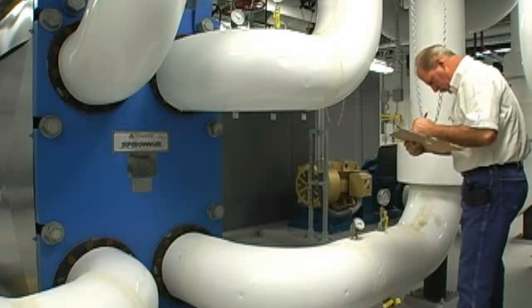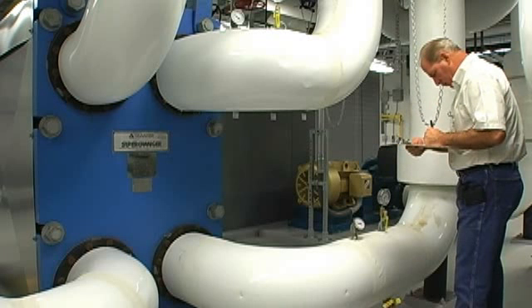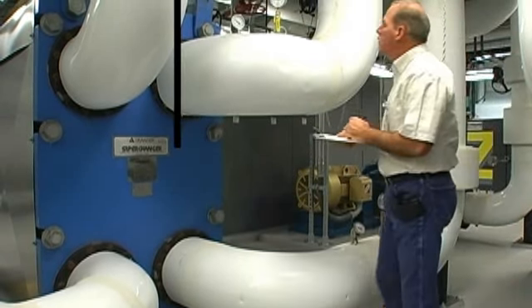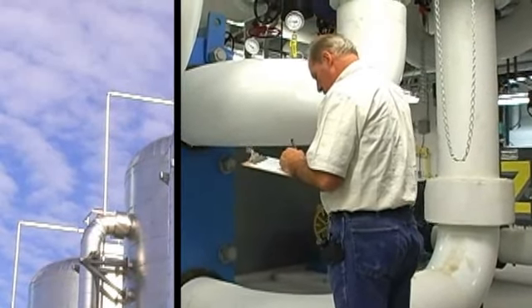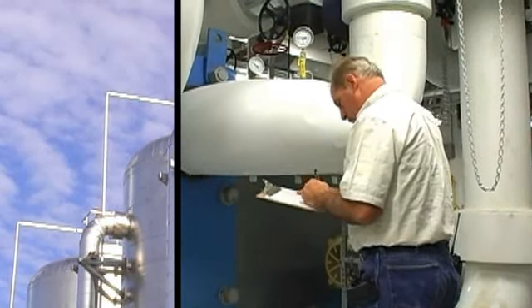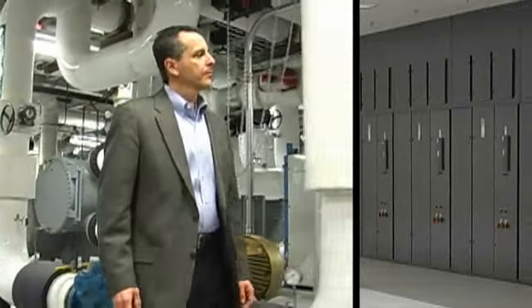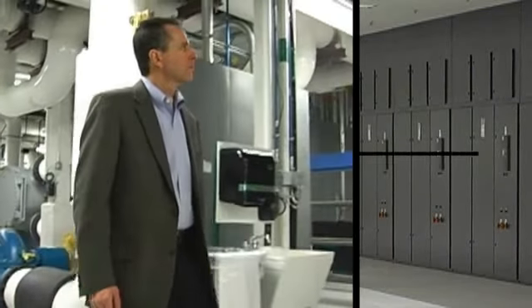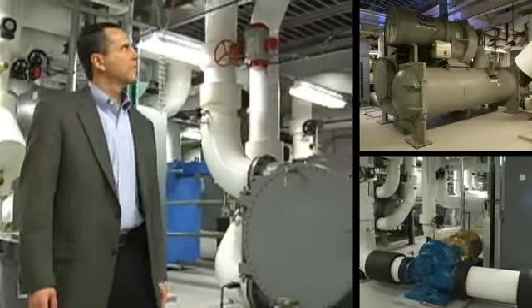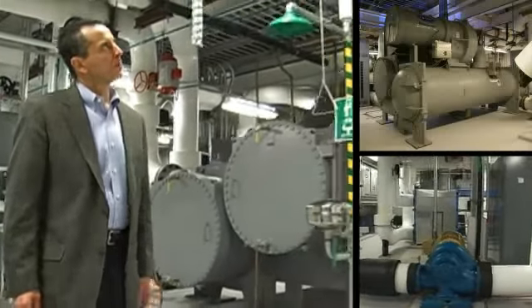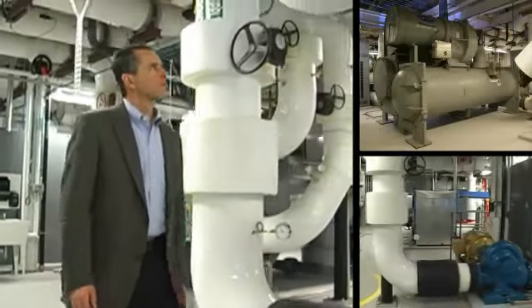These practices include free cooling from a waterside economizer, allowing us to use the outside temperature to cool the data center for 44% of the year. Variable speed controlled computer room air conditioners, pumps, and chillers allow us to provide cooling on demand, significantly reducing power consumption.